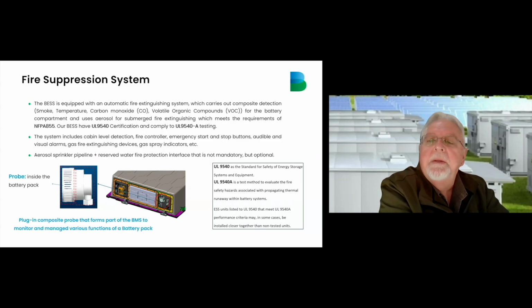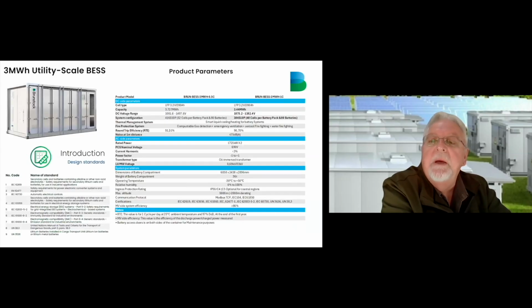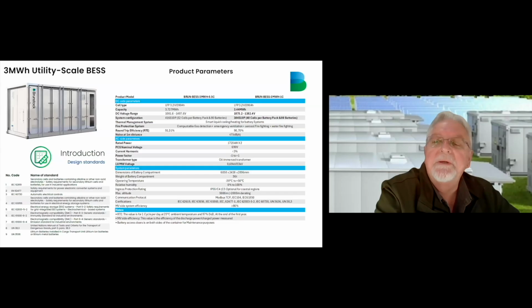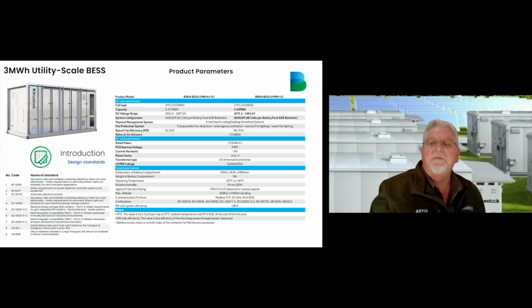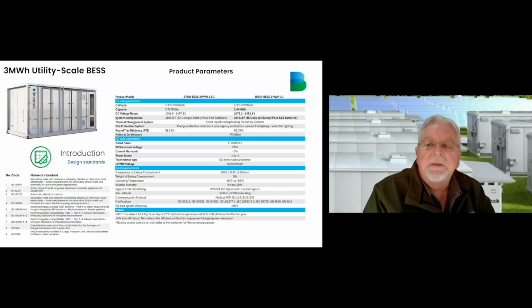Here is an example of the technical specification of a 0.5C, 1C, and a 1C 3 MWh liquid cooled BESS. It must comply with all the international standards as listed on the left-hand side. Cell ratings are 280 amp hours for both the 0.5C and the 1C configuration. The DC voltage is up to 1500 volt. Your PCS voltage is up to 690 volt. Your step-up transformer that we will use with the system is an oil-immersed step-up transformer that will step up your 0.69 kV voltage up to 11, 22 or 33 kV.